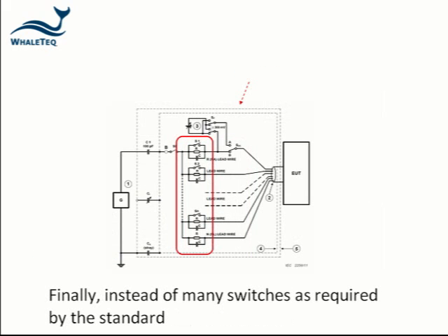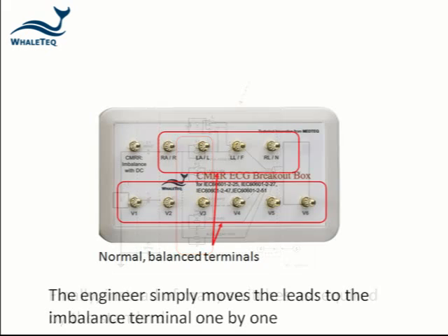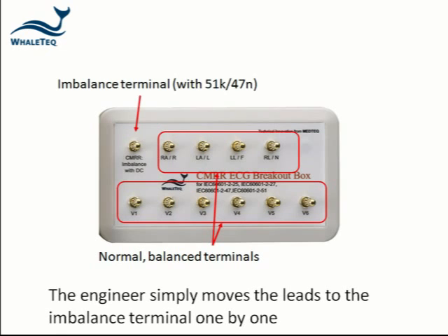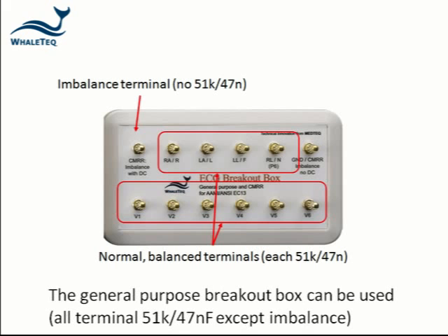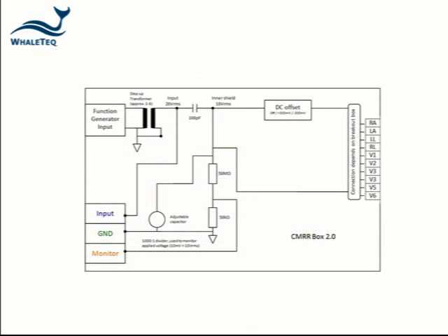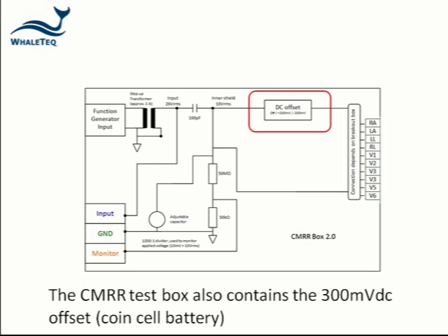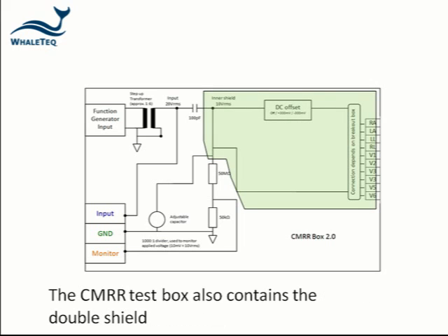Finally, instead of using many switches to create the imbalance, the engineer simply moves each lead electrode to the imbalance terminal one by one. The opposite configuration in the old 2-47 and the AAMI standards is implemented using the general purpose ECG breakout box. This breakout box accesses the alternate network inside the CMRR box. The box also includes the 300 millivolt DC offset powered by a small coin cell battery, the double shield, and an adjustable capacitor as required by the standard.